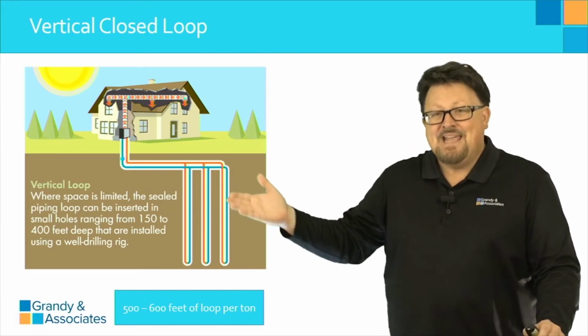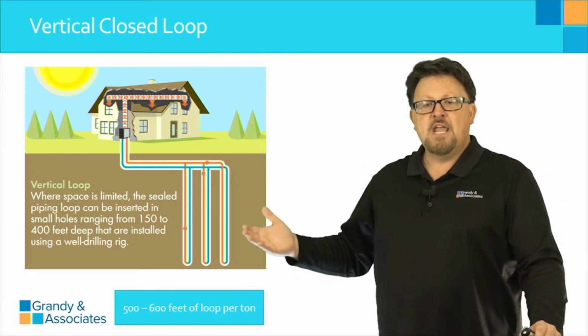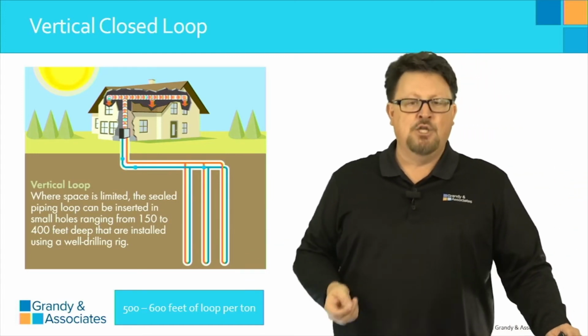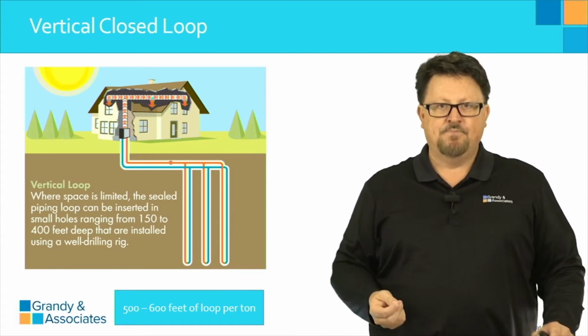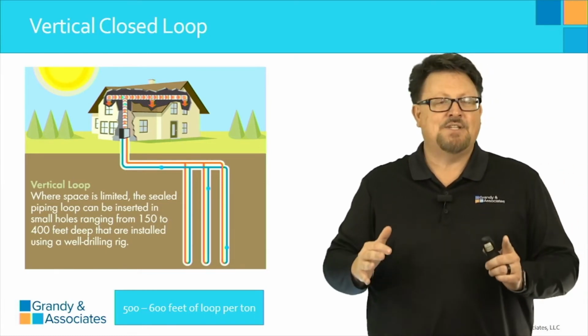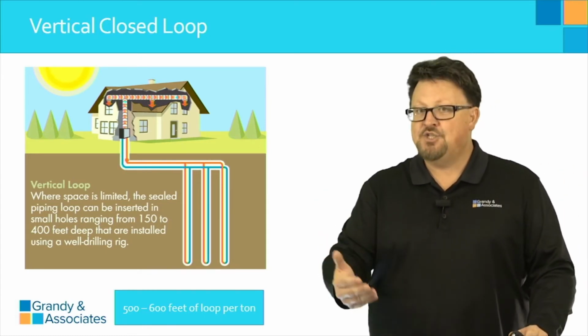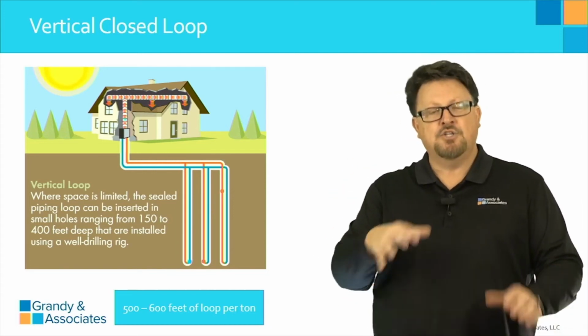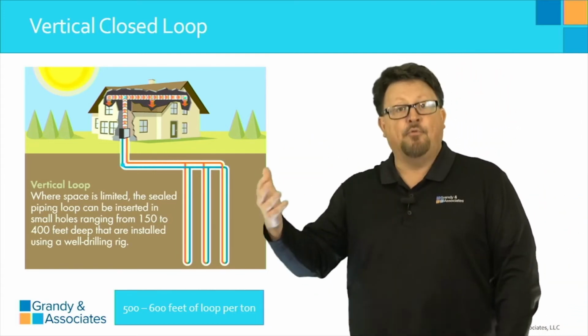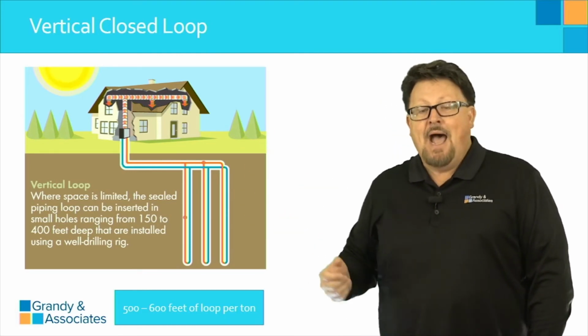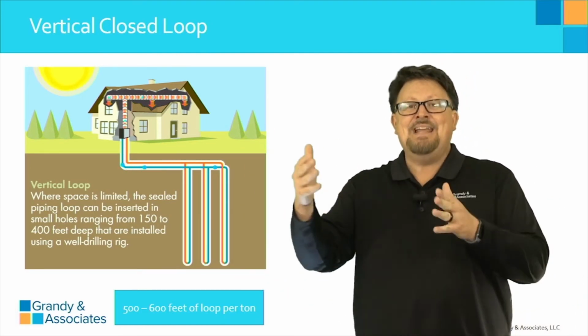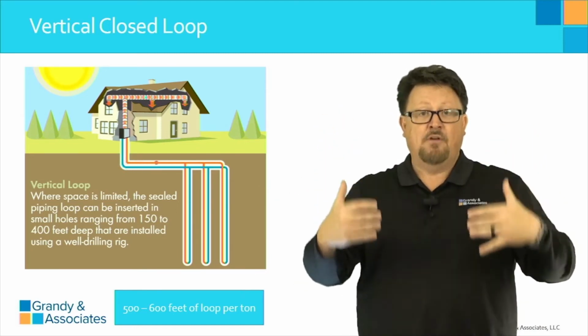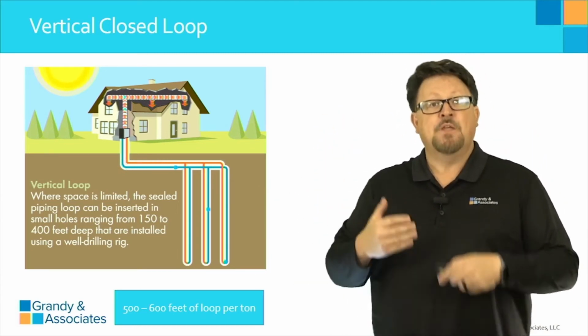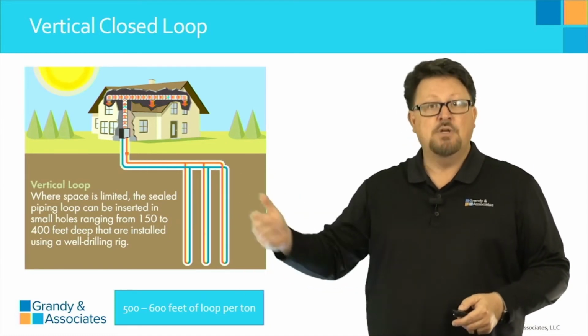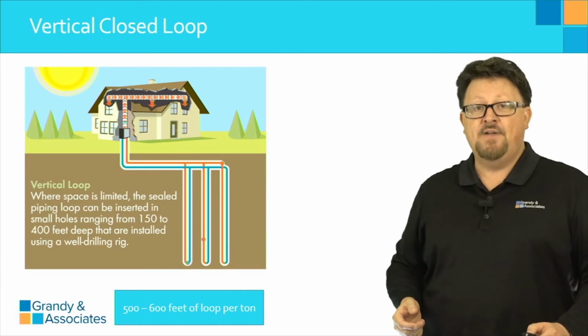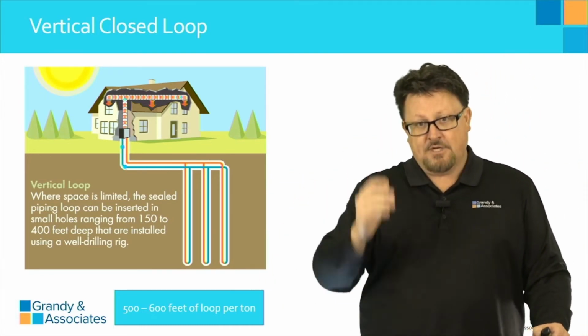Now, the depth can vary, but as a rule you're looking at about 500 to 600 feet of loop per ton of the system. In subsequent sessions of this study, we're going to define tonnage and how we calculate that. But just to give you an example, if I had a 3-ton geothermal system, I would need somewhere between 1,500 to 1,800 feet of loop for that system to function properly. So those are some of the dynamics that go into considering if geothermal would be a good fit from a design perspective for your customer.